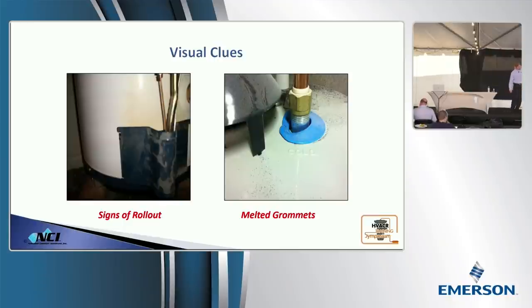Another one, what about signs of rollout or spillage? If you see discoloration around the burner compartment, we assume that flue gases always leave the heat exchanger, right? There's situations where they don't. And instead of leaving the exhaust, they spill out the burner compartment and they will discolor and rust anything that they come across. You guys ever seen water heater bases like that? They're kind of discolored and you think, why is it dirty and brown like that? That's flue gas spillage. And it's discoloring the paint on that water heater. You'll also see melted grommets. No cold water, not even in Phoenix, Jake, is gonna melt that cold water grommet. All right, maybe. So if you see that, that's flue gas spillage. It won't always cause the rust. So these are just some quick visual clues that you guys can look for.